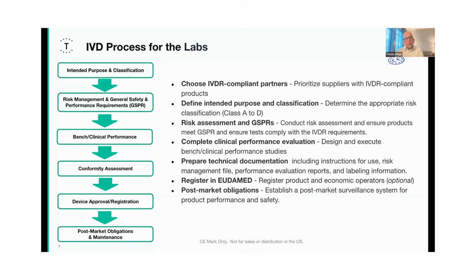We need very good clinical evidence, and then we have a conformity assessment. Now, not all products need to go through the full conformity assessment, if you have some ISO certification. So you have the ability to reduce your conformity assessment, but there is still a minimum required with regards to how the product conforms to the disease indication, as an example. So the outcome of the review by a notified body, an authorized rep, or a competent authority is that we get a device approval and registration, and then we focus on the post-market obligations like complaint handling, and also the clinical evaluation, which has to be performed annually, and all the post-market surveillance gets fed into the clinical evaluation.